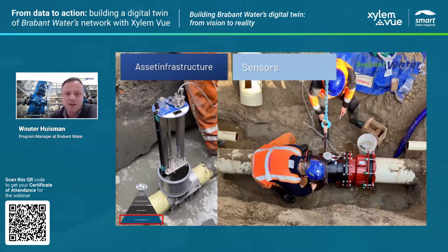of this DMA. So we set up the flow meters, and at the flow meters, there is also a pressure and a temperature sensor. And in the DMAs, and that's what you see on the left, we have this so-called smart probe by Pipelife. This is a battery-fed pressure sensor, so that we also can measure the pressure within the DMAs. We are installing about 500 of the pressure sensors and 400 of the flow meters, so about 900 to 1,000 sensors in total.